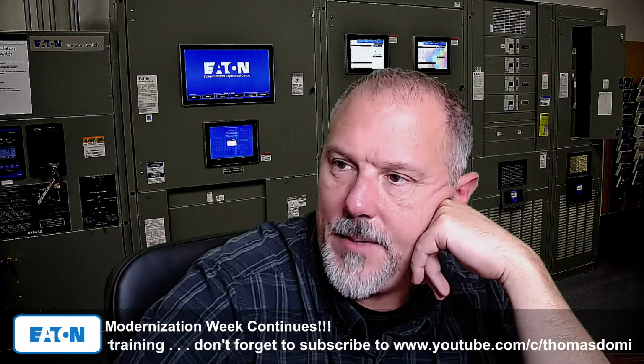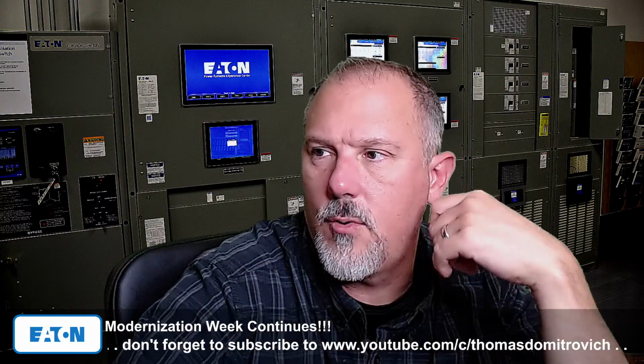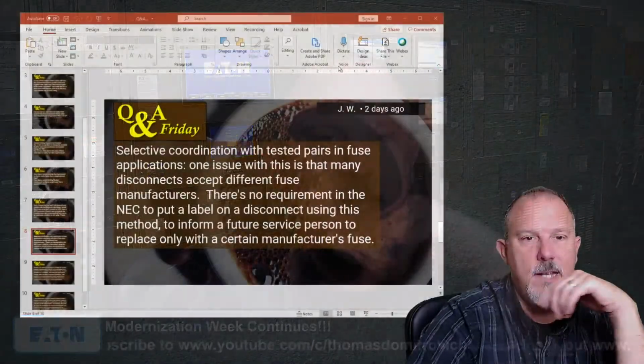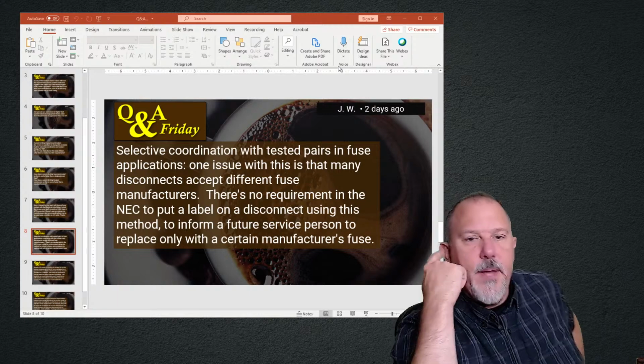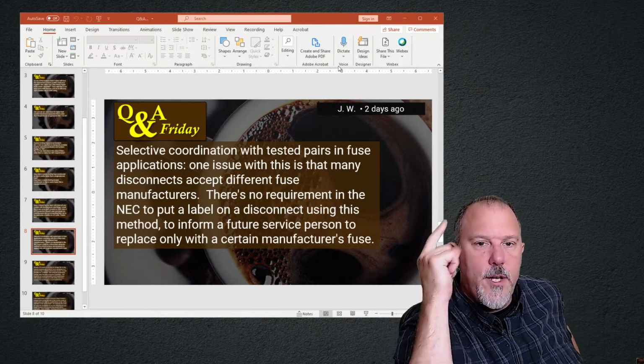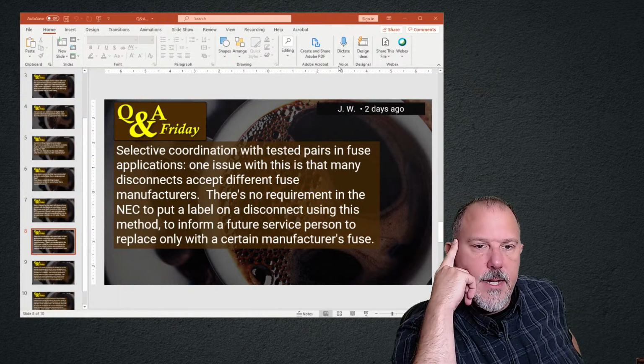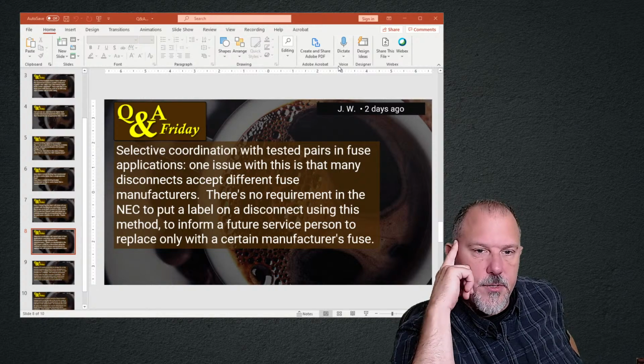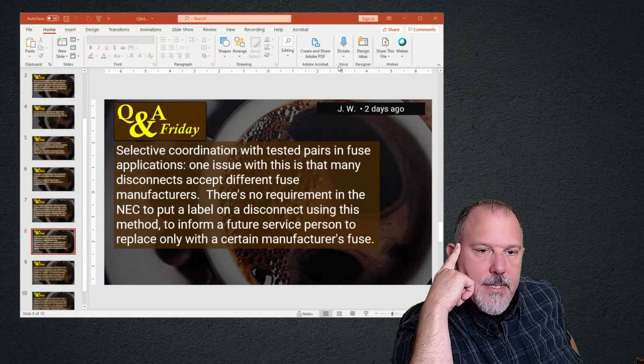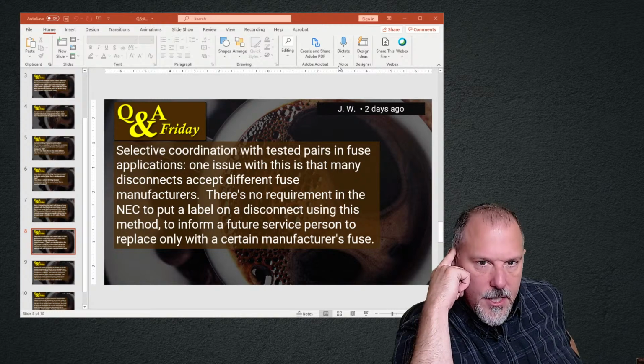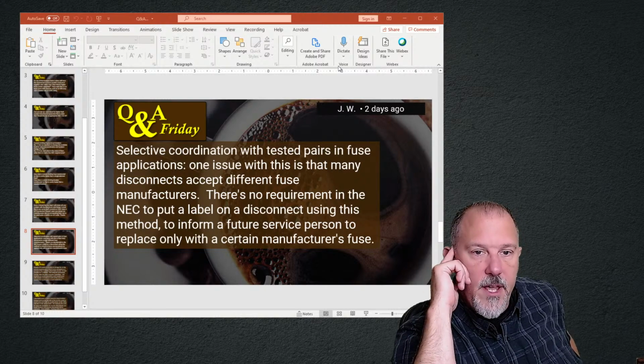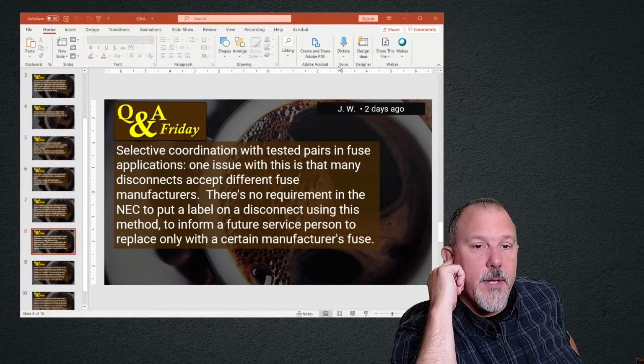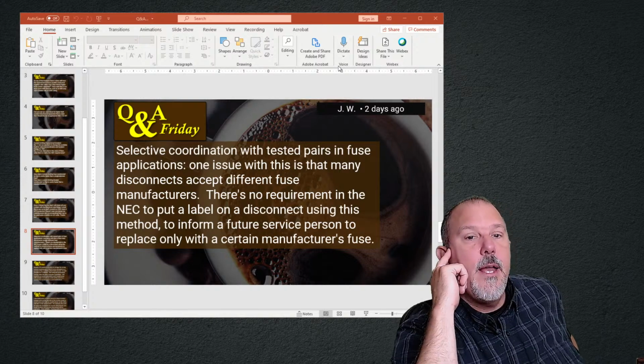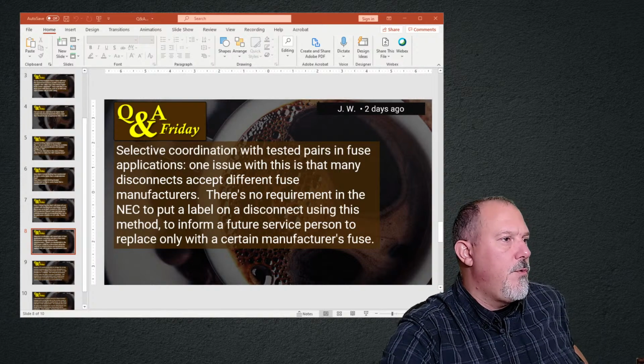There's no requirements in the NEC to put a label on a disconnect. All right. Well, let me answer this one first. It says selective coordination with tested pairs in fuse applications. One issue with this is that many disconnects accept different fuse manufacturers. There's no requirement in the NEC to put a label on a disconnect using this method to inform a future service person to replace only with a certain manufacturer's fuse.